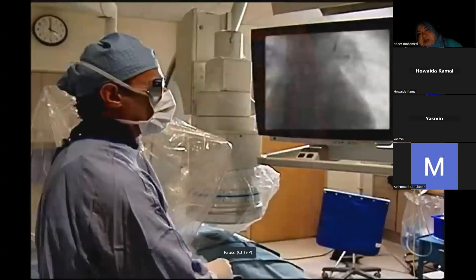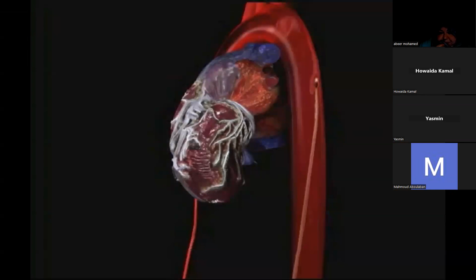Reposition if necessary. An intra-aortic balloon can, under unusual clinical conditions, be inserted into a false lumen of the aorta. If you suspect that a balloon is positioned in a false lumen, inject a radiocontrast medium through the inner lumen of the balloon catheter while observing under fluoroscopy. If the catheter is in the appropriate space, the contrast medium will dissipate within the next several inflations of the balloon. If the contrast medium remains at the balloon tip with initiation of pumping, suspect positioning in a false lumen and remove the balloon catheter immediately.